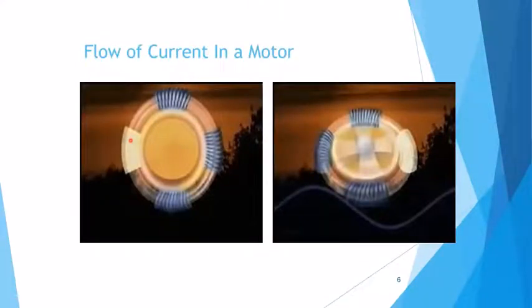So what I like to do is bring it back to the very basics of what we're really doing and what we're really operating. I've been a motor winder since I was 10. My father started me winding coils for motors and helping insert them when I was a little bit older, and then understanding electrical connections inside the motors. What we're basically doing is, typically, like this shows a 4-pole stator. That's only one phase. So a 3-phase will actually have 3 sets of these operating inside the motor.